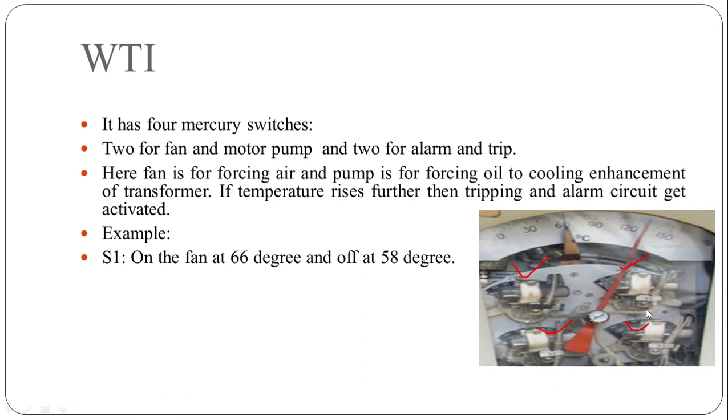Suppose if temperature of transformer further rises then better cooling need is arising. So in that case switch 2 gets operated. When switch 2 gets operated then pumps get turned on. So suppose switch 2 gets operated at 76 degree of temperature. When temperature reaches 76 degree then pumps get turned on by switch 2.